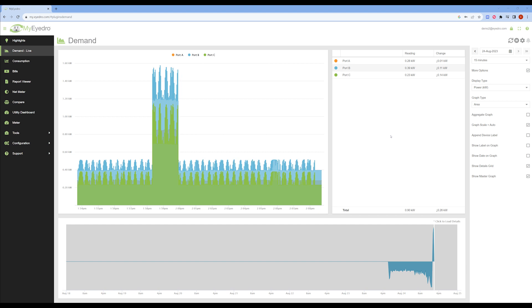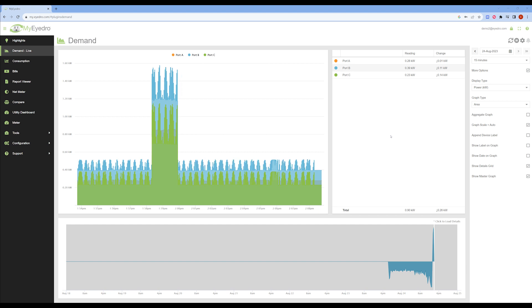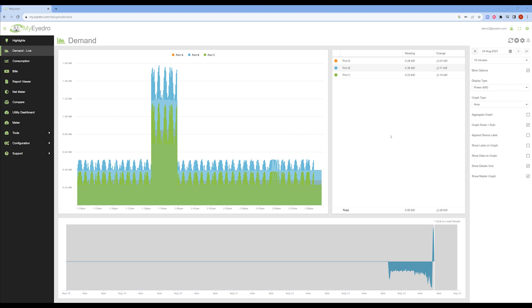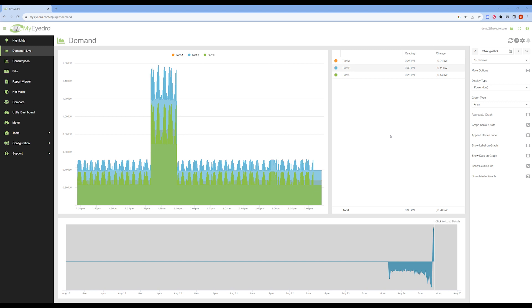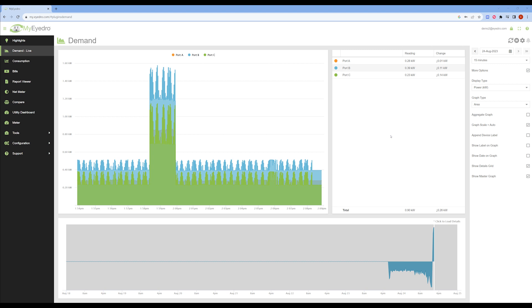It's important to note that when running multiple lines through a sensor, their ratings are additive. For example, running three 200-amp lines through a single sensor will require that it's rated for at least 600 amps.